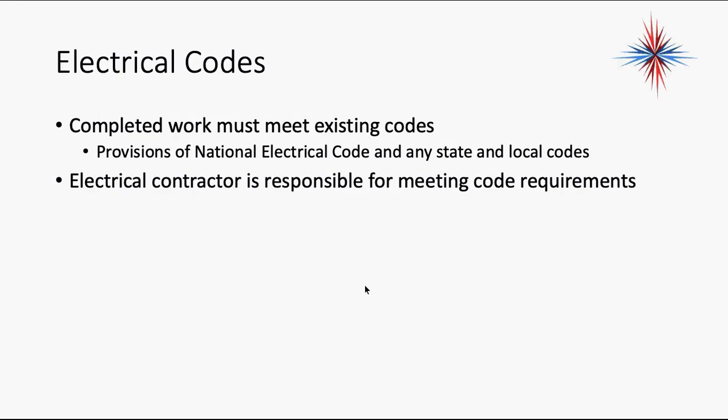Now, part of the National Electrical Code and part of the International Mechanical Code says you will pull a permit. So make sure you pull permits for things you install. Because once that inspection is done on a permit, the responsibility and the liability shifts from the installing contractor to the city or county, whoever the permit was pulled through and did the inspection. So permits are very important.